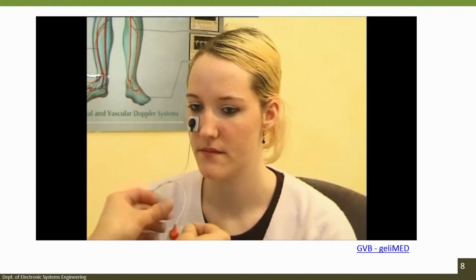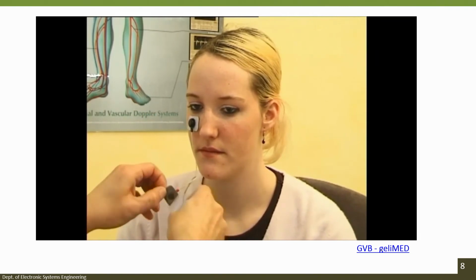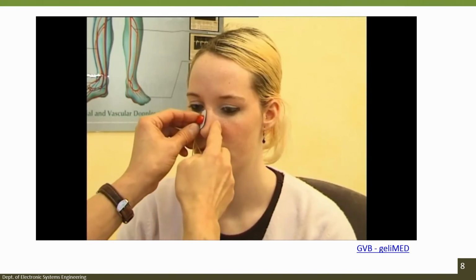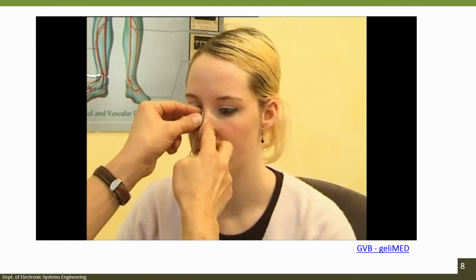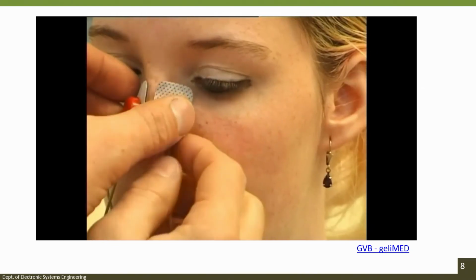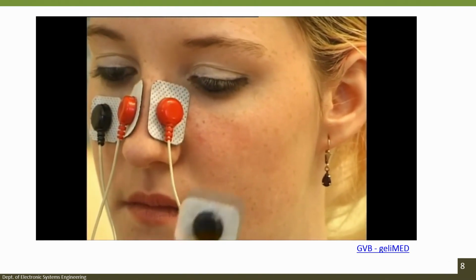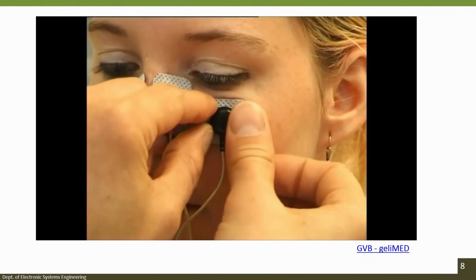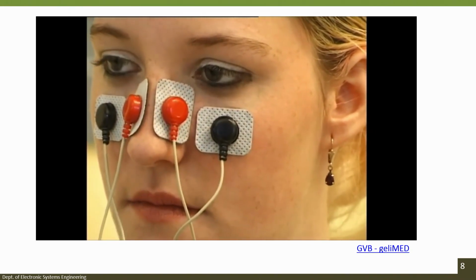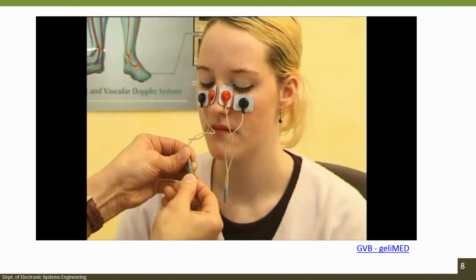Specialized forms of neurography like the F-wave, or as shown in our example, the blink reflex, can be applied extremely well using disposable adhesive electrodes or disposable adhesive snap electrodes. The respective reference electrodes are attached above the nasal wings, and the active electrodes are attached above the respective orbicularis oculi. These electrodes can then be connected to the EMG instrument using the multifunctional cable.